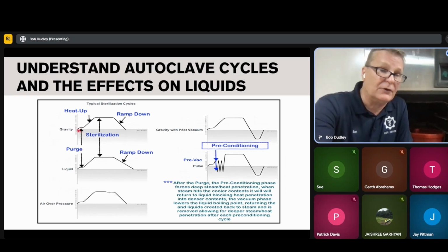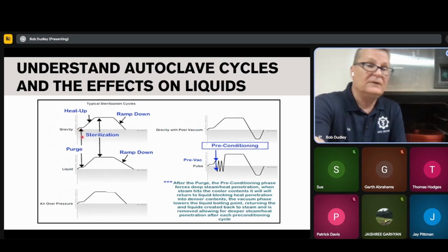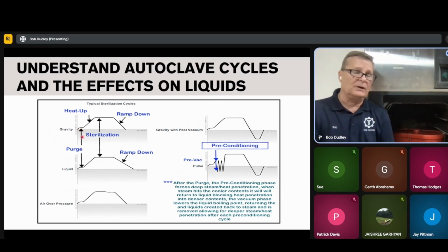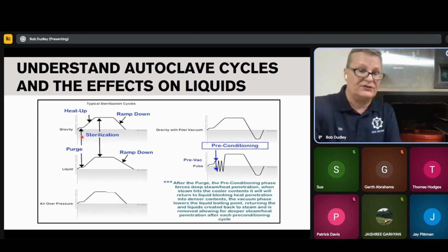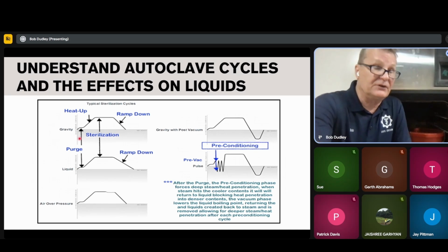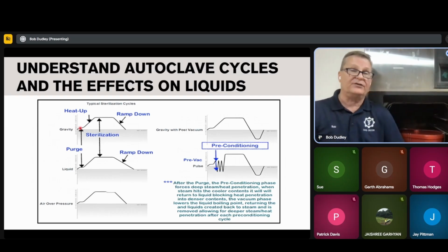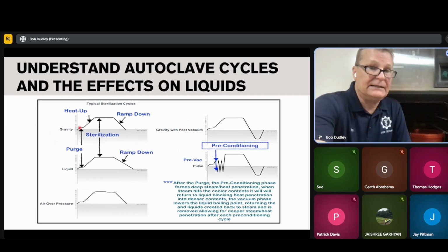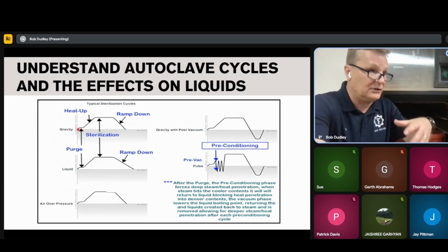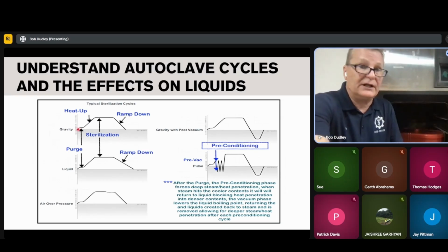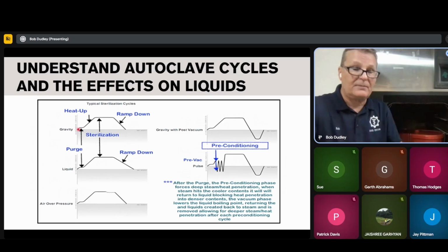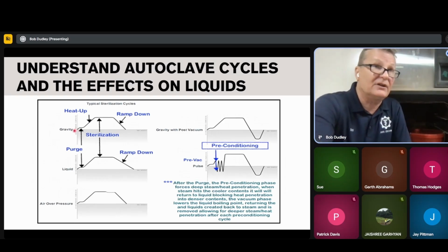Here you have what they call the purge on the cycle. Now, when you close the door, you put everything in. Most of you guys are operating, even the hospitals, at 68 degrees. The stuff is pretty chilled up. So what they do is they run this purge section in here, and it runs between 1 to 3 minutes. What that purge is doing is it's taking away every air pocket, literally everything that's in that autoclave. And of course, the door was open, and if you get an air pocket, it'll just condense and it will not heat up even under pressure.